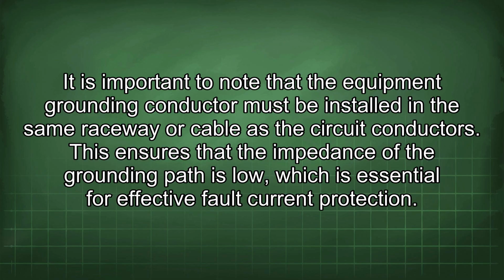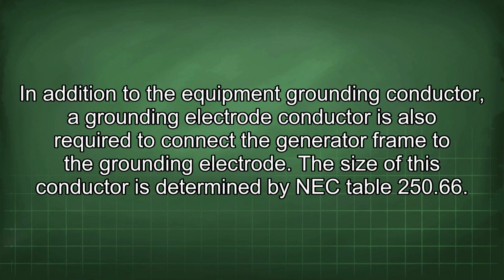It is important to note that the equipment grounding conductor must be installed in the same raceway or cable as the circuit conductors. This ensures that the impedance of the grounding path is low, which is essential for effective fault current protection. In addition to the equipment grounding conductor, a grounding electrode conductor is also required to connect the generator frame to the grounding electrode.